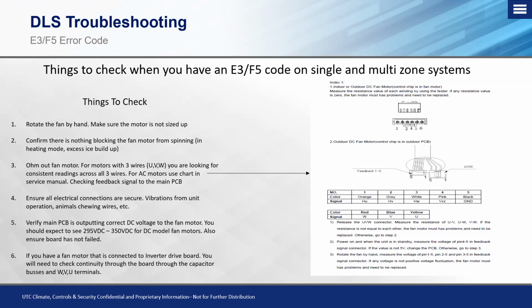Well, then we need to focus on the wiring harness going to the fan motor and the actual fan motor itself, and that's where we would start ohming out our fan motor, checking wires, checking electrical connections. So they essentially go hand in hand. It's just ruling things out one by one, just like we do with any normal troubleshooting process. Okay. And then finally, if you have a fan motor that is connected to an inverter drive board.